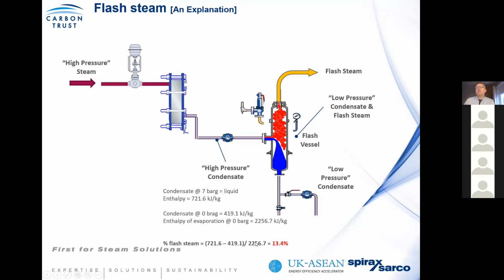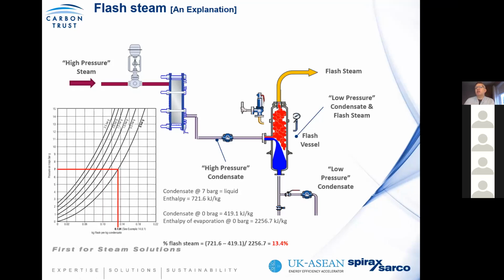And when we look at the enthalpy of evaporation, about 13% of the condensate will convert to flash steam. Again, unavoidable and often seen as flash steam coming from condensate recovery systems, because in reality, in most cases, you're going back to a condensate recovery unit. For your own application, we mentioned the tools and literature we have freely available. So you can see there are sizing charts where you can very quickly see, from the pressure of your application and the pressure of your condensate, exactly how much flash steam it will theoretically create. And again, in knowing this, you can then see how you can improve the efficiency for those users.